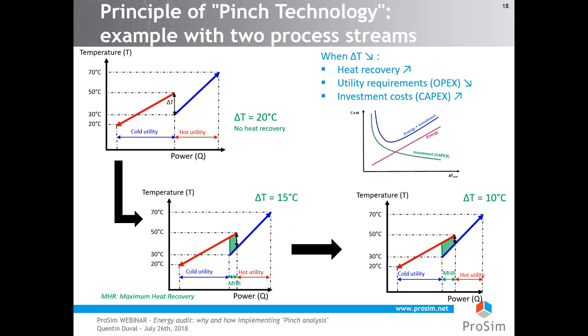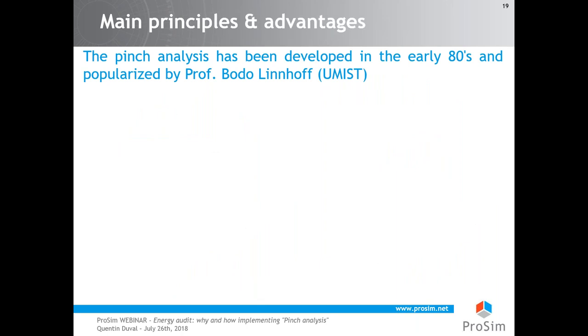If we overlap the curves to a temperature deviation of 15°C, part of the hot stream is cooled by the cold stream — this green area is named the maximum heat recovery. The remaining parts still need utility heating and cooling. As the temperature deviation decreases, the maximum heat recovery increases and the utility needs decrease — this deviation is named the pinch, which explains the name of the method. However, a smaller pinch means a larger heat exchanger surface area and higher investment cost, so an optimal pinch value can be found.